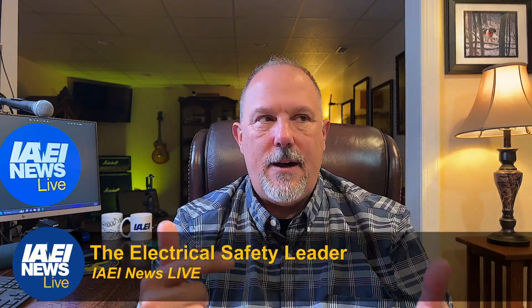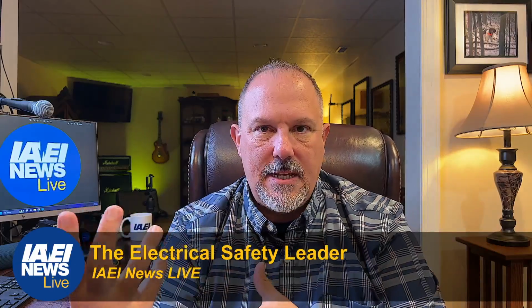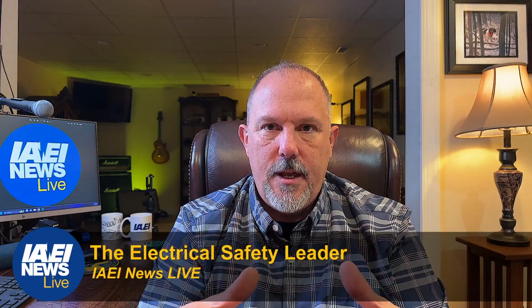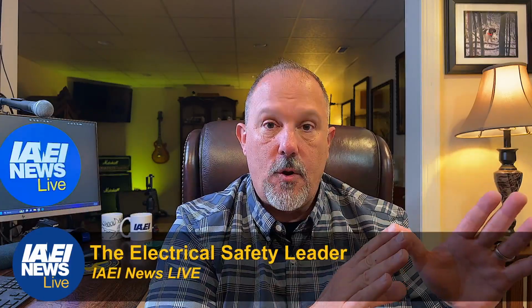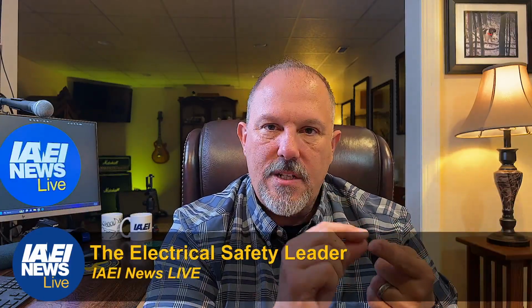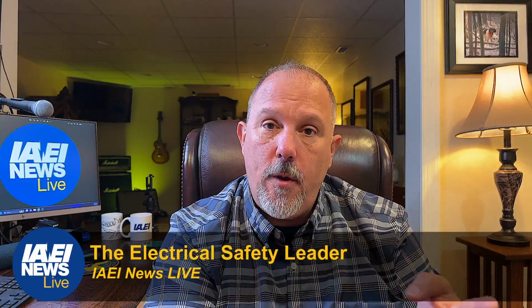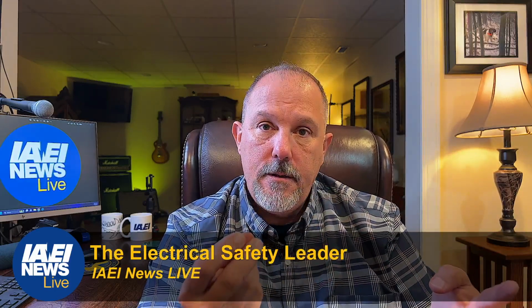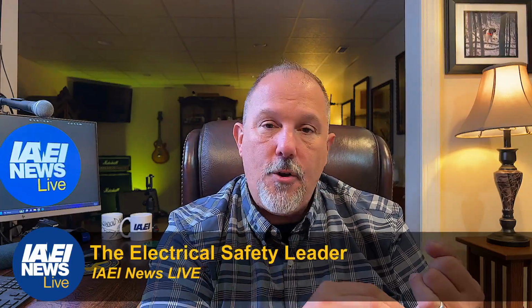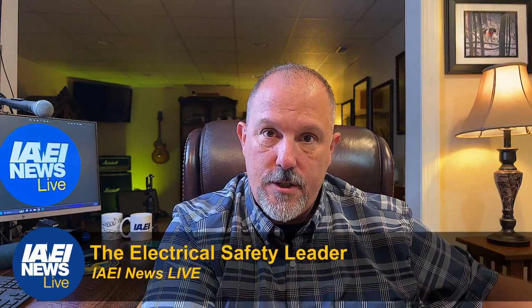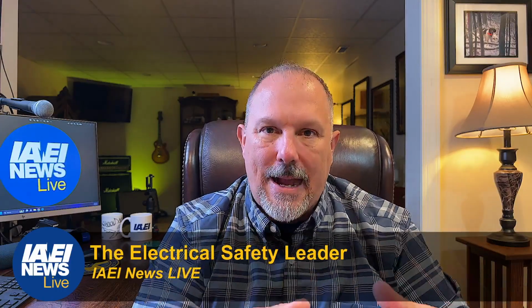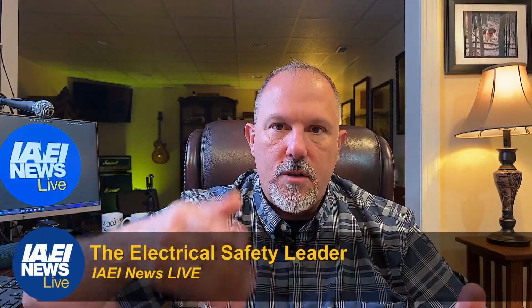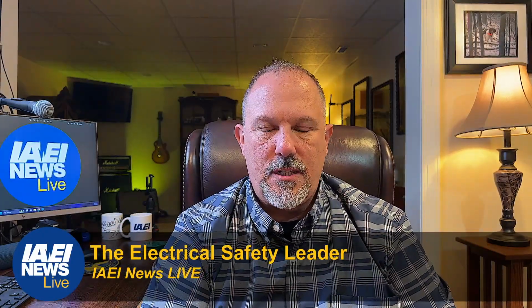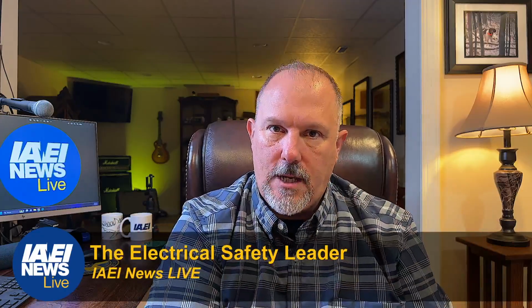Understand, and when you're thinking about what you think might be missing here, you have to understand how these documents work together. The National Electrical Code is your installation requirement. That's where you're going to find how you establish the bond, the right terminations, the right equipment to establish that bonding of the power system, how you establish the earthing, the ground in the power distribution system, the practices of not having multiple grounds in a power distribution system. You want to bond everything, bring it all back to one location. That's an installation requirement. That's not a maintenance requirement.